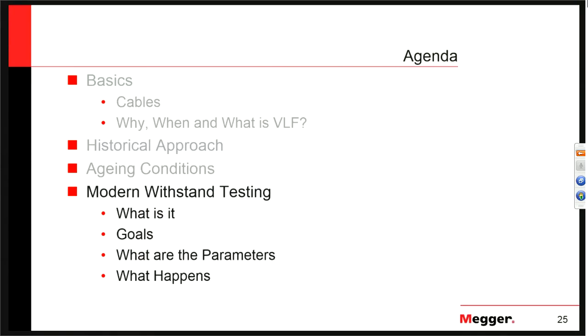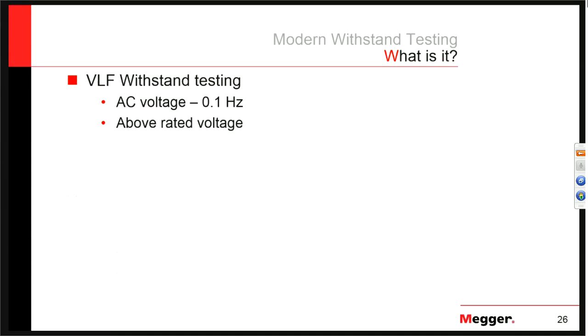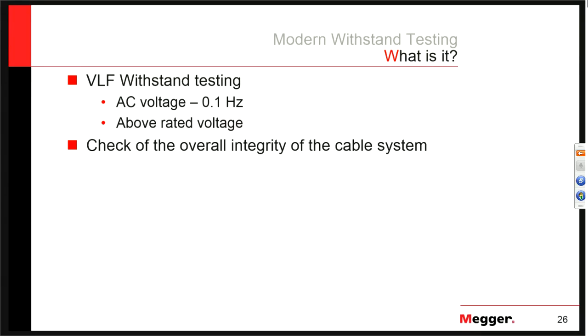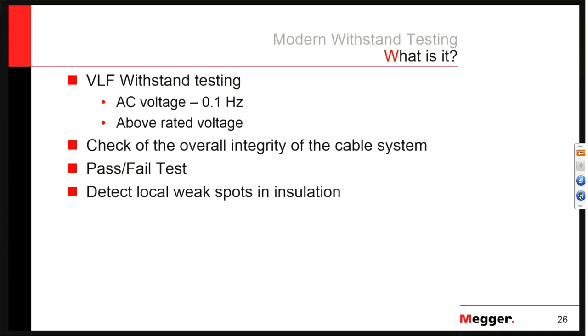When we talk about modern VLF withstand testing, what are the parameters and what is actually happening? VLF testing is AC voltage at 0.1 Hz, at a voltage above rated voltage selected based on IEEE standards — putting pressure on the cable to find weak spots. VLF testing is a check of the overall integrity of the cable system. In its basic form, VLF withstand testing results in a pass-fail test. The goal is to detect local weak spots in the insulation by causing existing weak spots to fail during our scheduled test time.